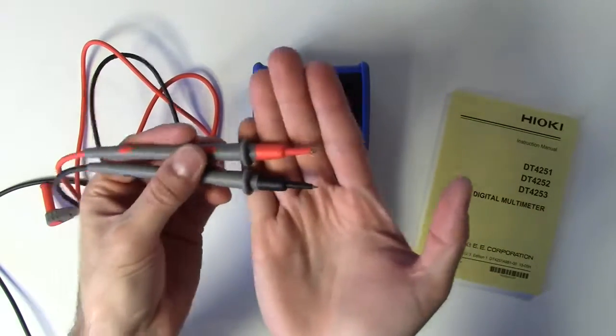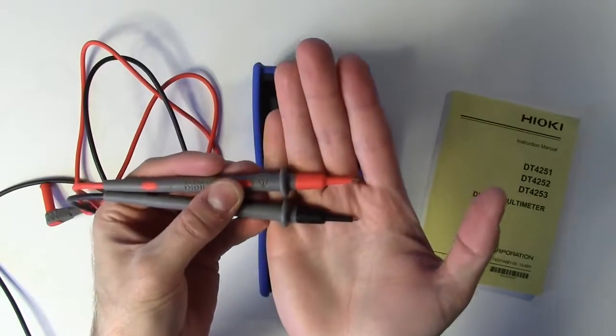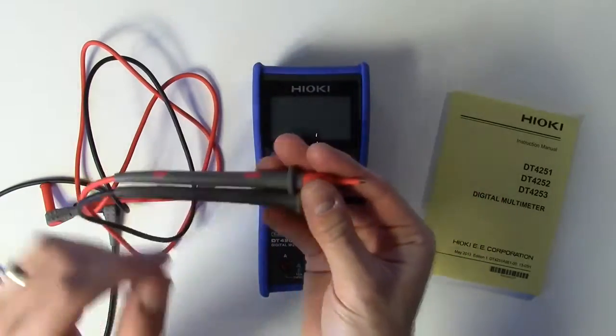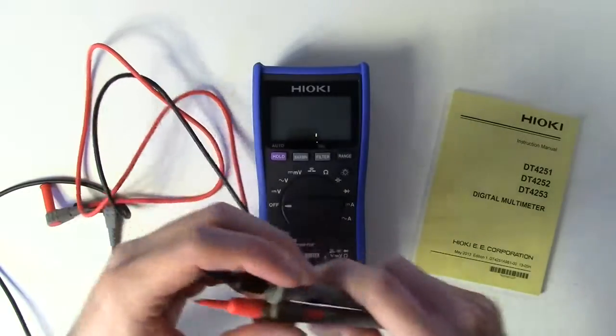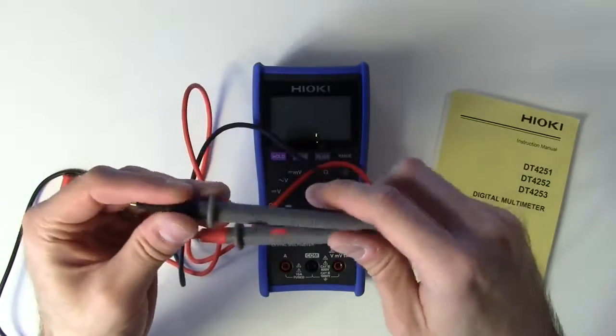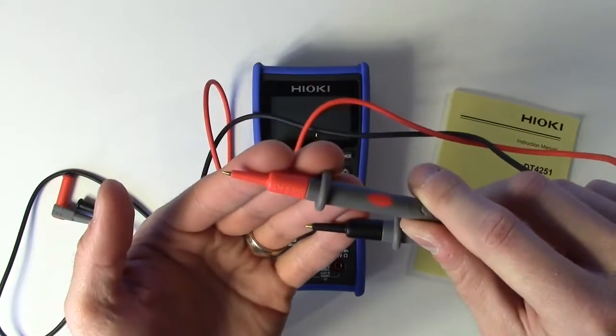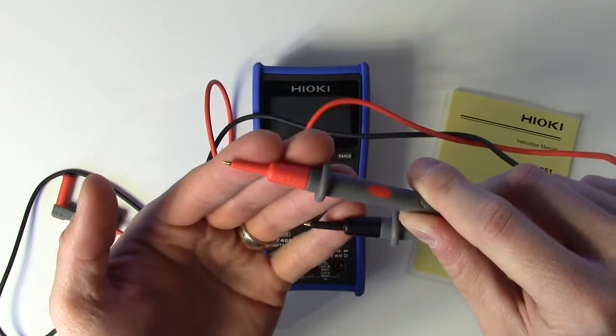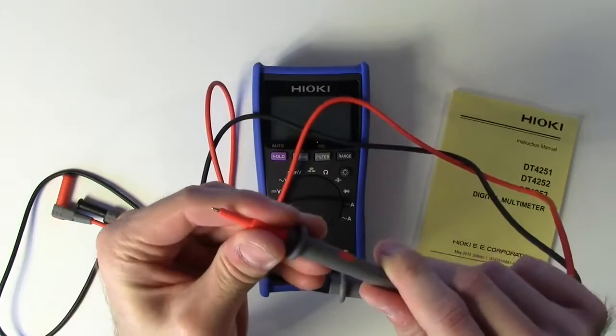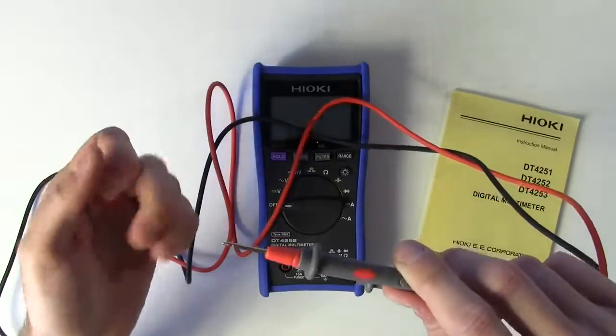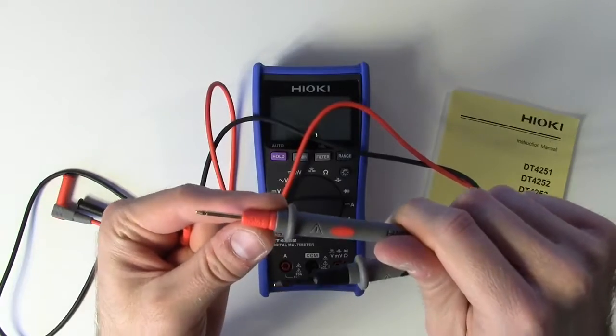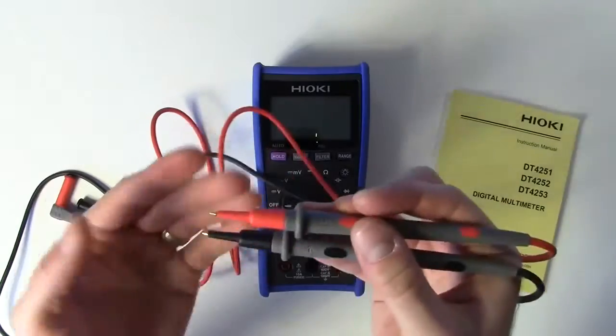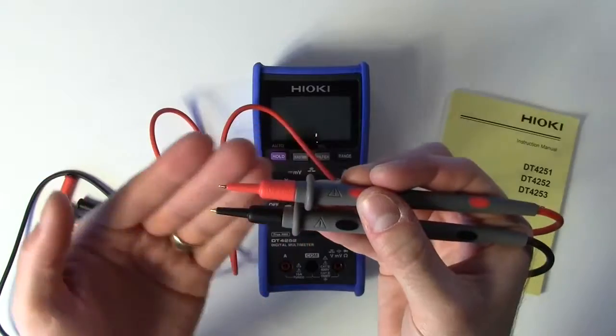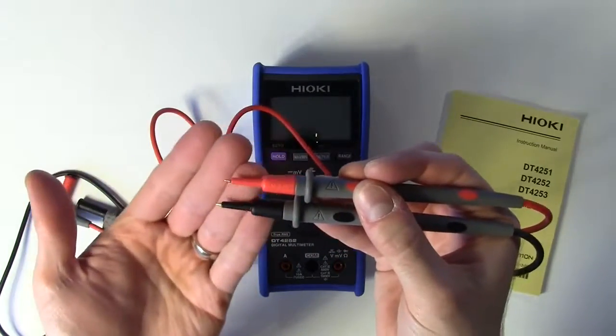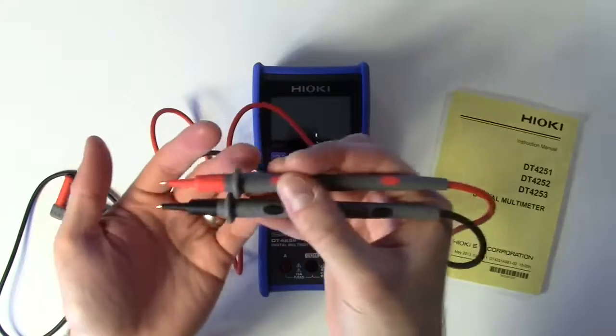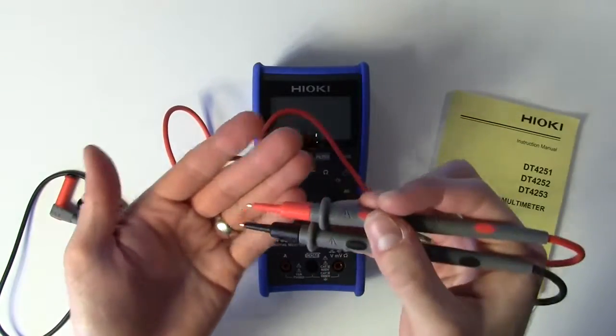They have the fully shielded probe tips. This is also part of, I believe, the new regulations. And these particular probes are perfectly matched for the capabilities of the meter. On the probe tip covers, they're listed as being Cat 4 600 volt and Cat 3 1000 volt. And then if you yank the probe covers off, which is pretty easy, they're listed there as Cat 2 for 1000 volts. I really like the design of these probe tip covers. They're not overly bulky. They don't get in the way if you need to get deep into something, like if the lead you're trying to get at is fairly crowded.